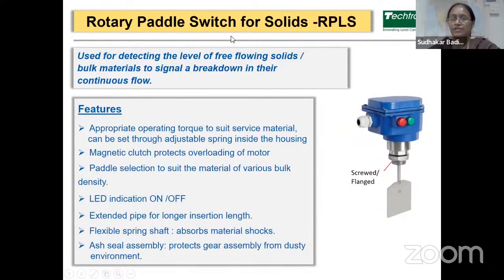Now this is a rotary paddle switch for solid applications, that is powders and granulars. It is used for detecting the level of free flowing solids or bulk materials to signal a breakdown in their continuous flow. It has an appropriate operating torque to suit the service material, which can be set through an adjustable spring inside the enclosure. The magnetic clutch is provided to protect the motor from overloading. The paddle selection can be made according to the bulk density of the material.